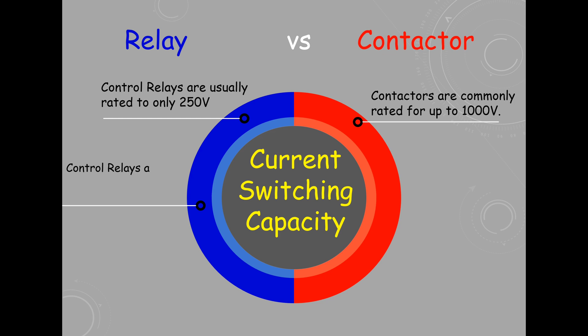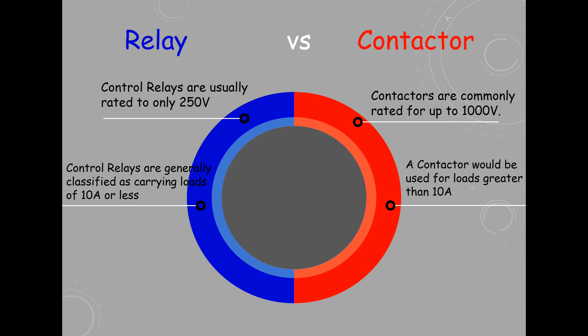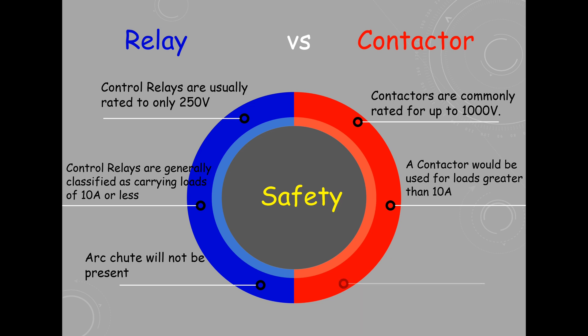Relays are generally classified as carrying loads of 10A or less, while a contactor would be used for loads greater than 10A. The arc suppression system is not present in a relay for safety, but the arc suppression system and spring must be present in a contactor for safety.